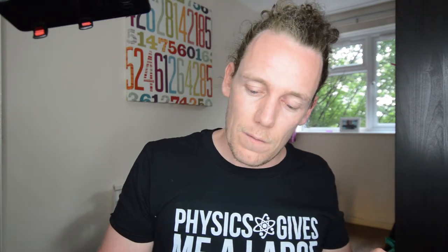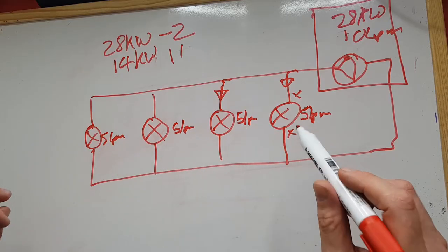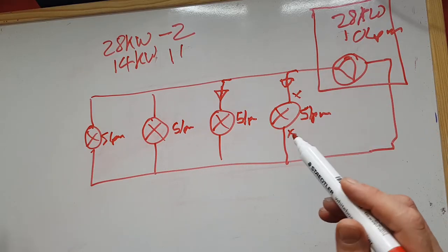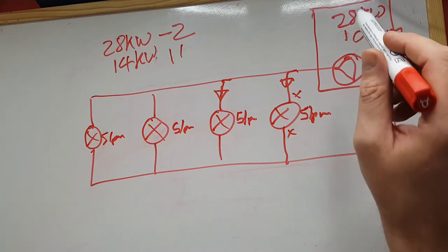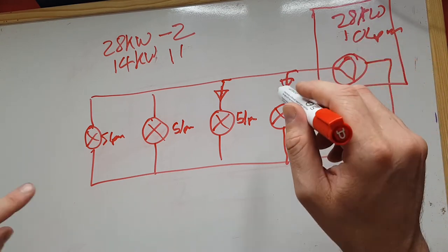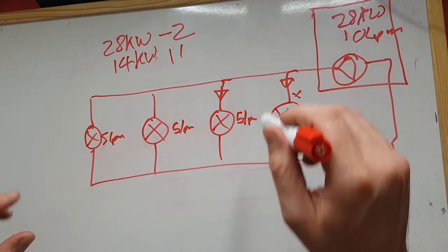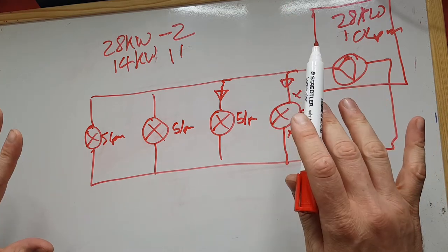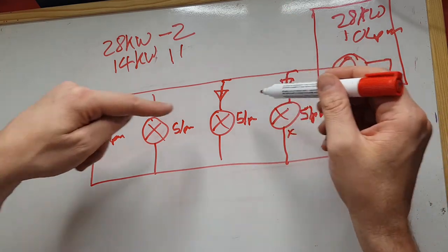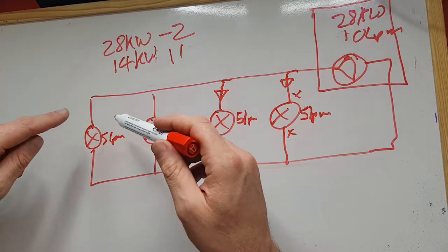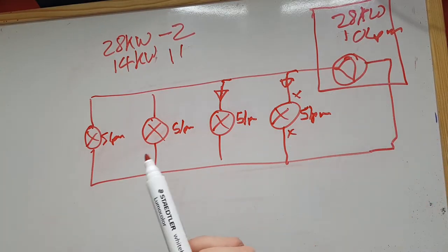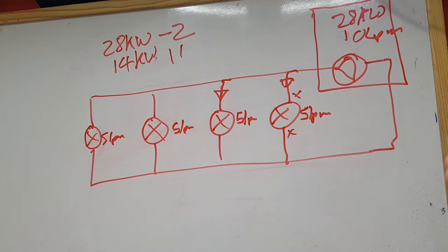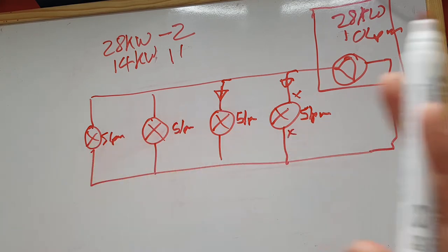Pressure dependent control valves, however, vary the amount of flow through each circuit depending on the pressure differential. So as this boiler slows down and the pump slows down, the pressure differential across a circuit will automatically go down with it. And because the pressure differential across each control valve — or lock shield, to you and me — drops, the flow rate will drop.